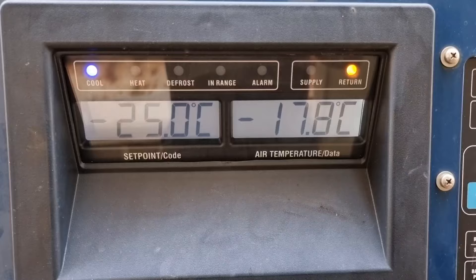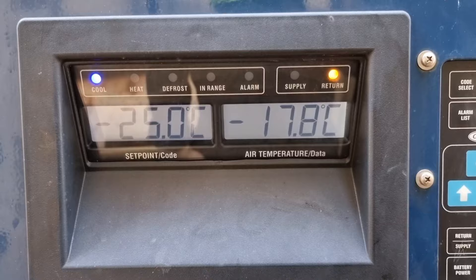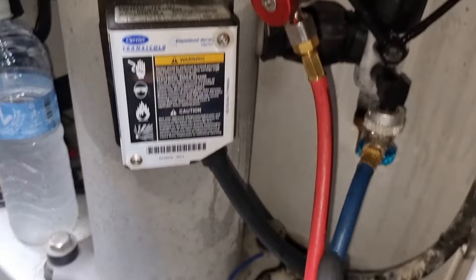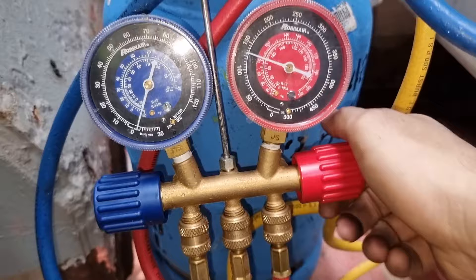Hello guys. For today's video, we are going to fix this refrigerated container. As you can see, the set point is minus 25 degrees Celsius and it can only get up to minus 17.8 degrees Celsius. Checking the sight glass, we are having a low refrigerant. I am also going to teach you how to do the proper charging of refrigerant inside this refrigeration system, and how we will avoid diffusing this refrigerant into our environment. Come and join me in this new learning.